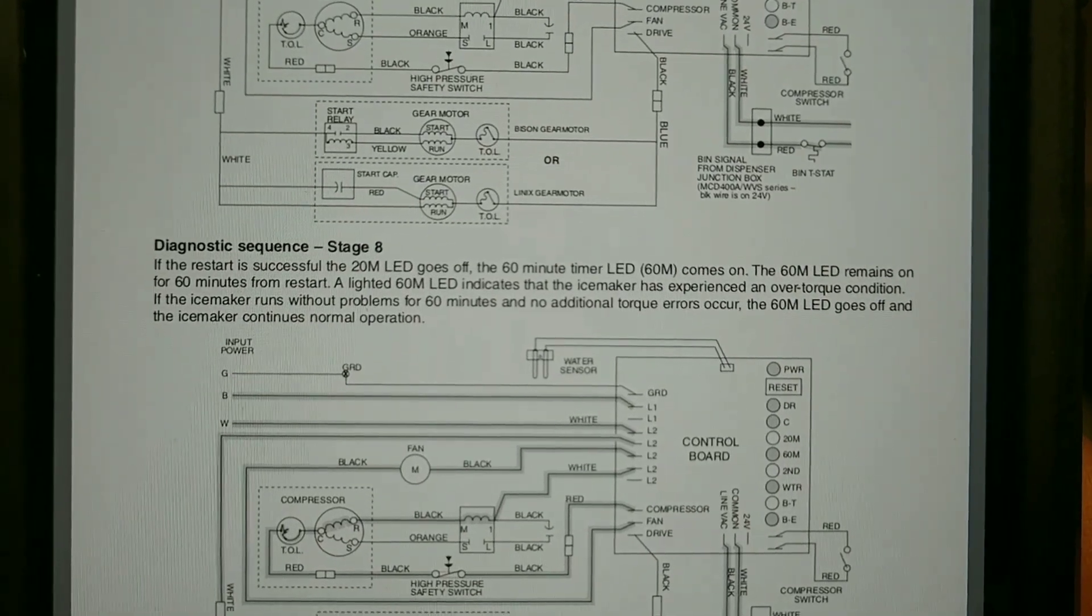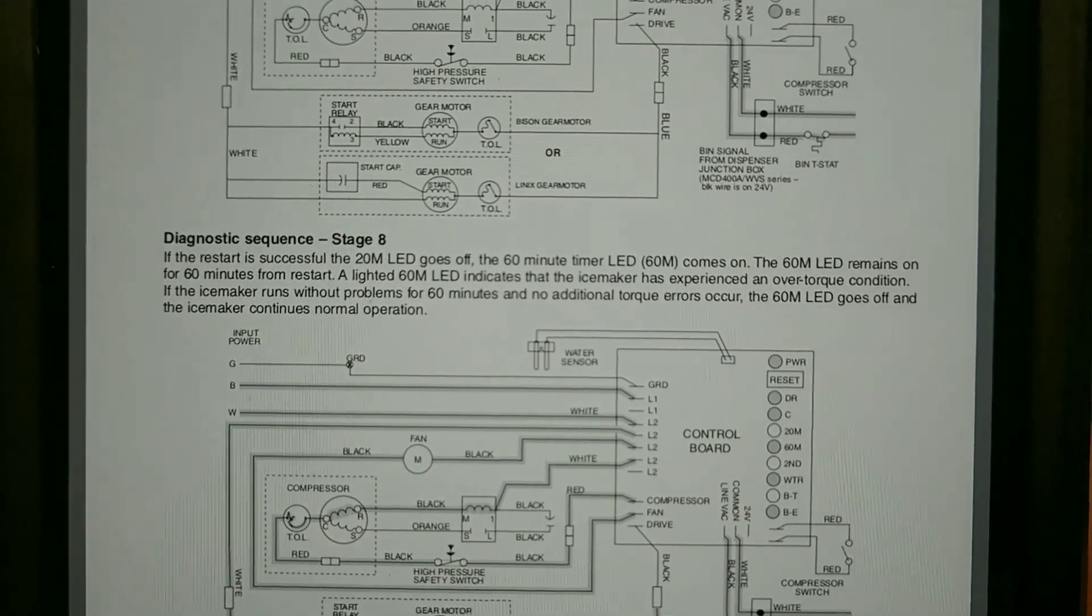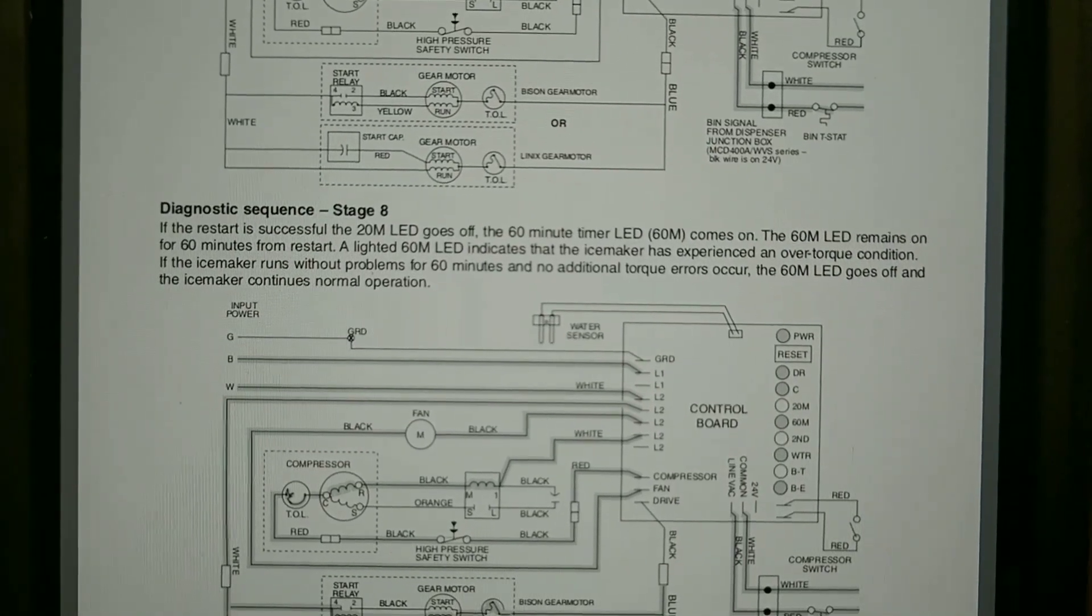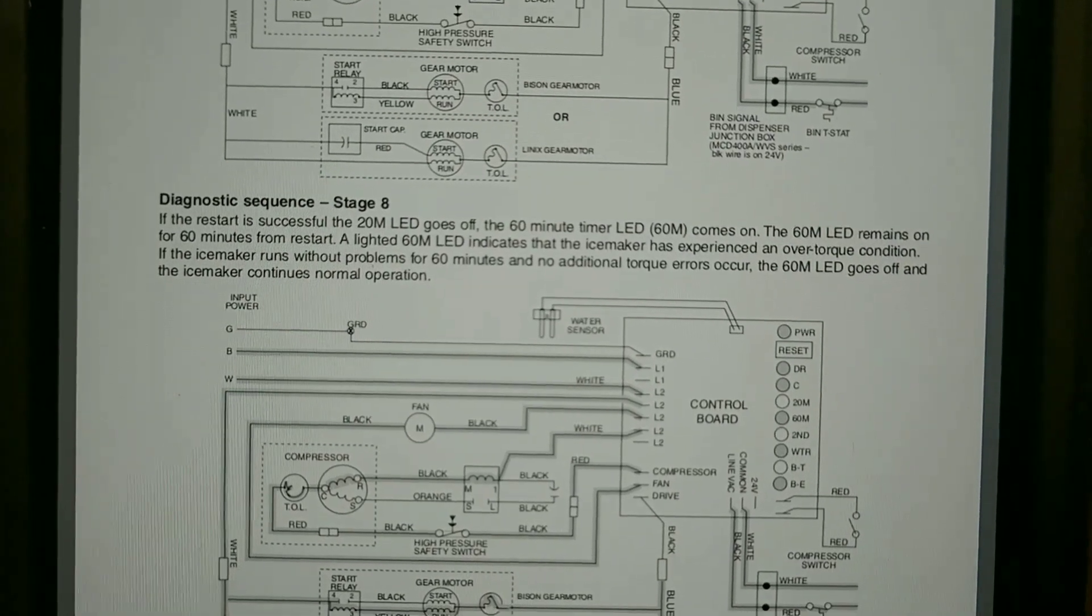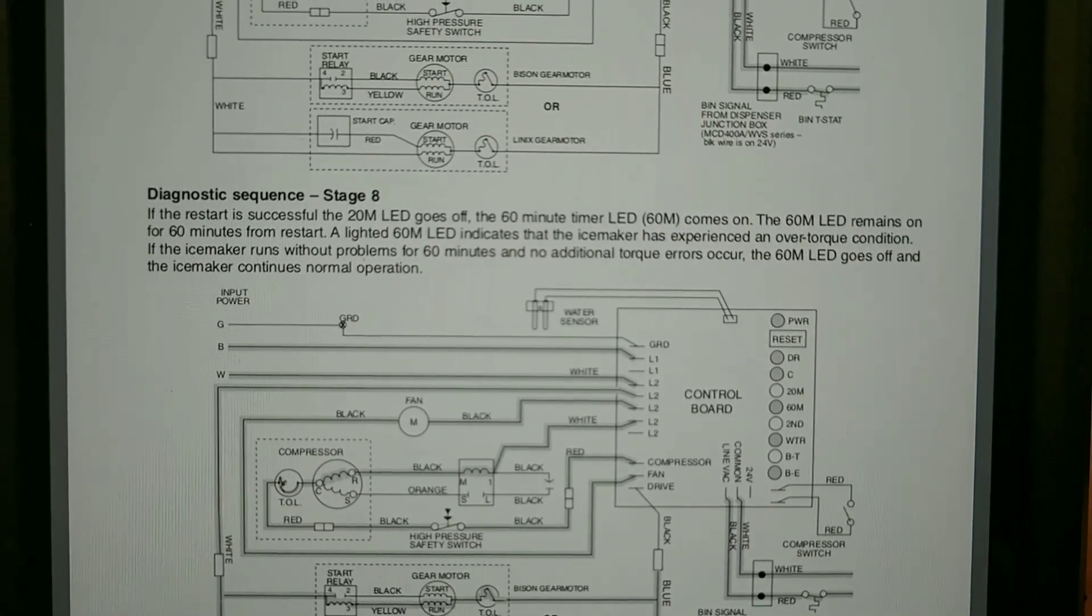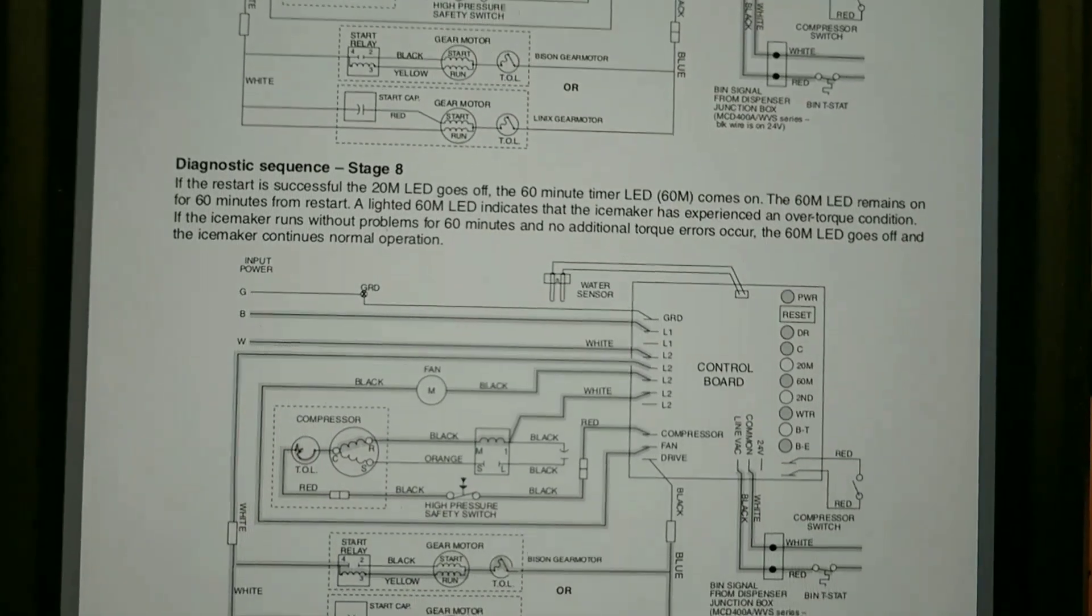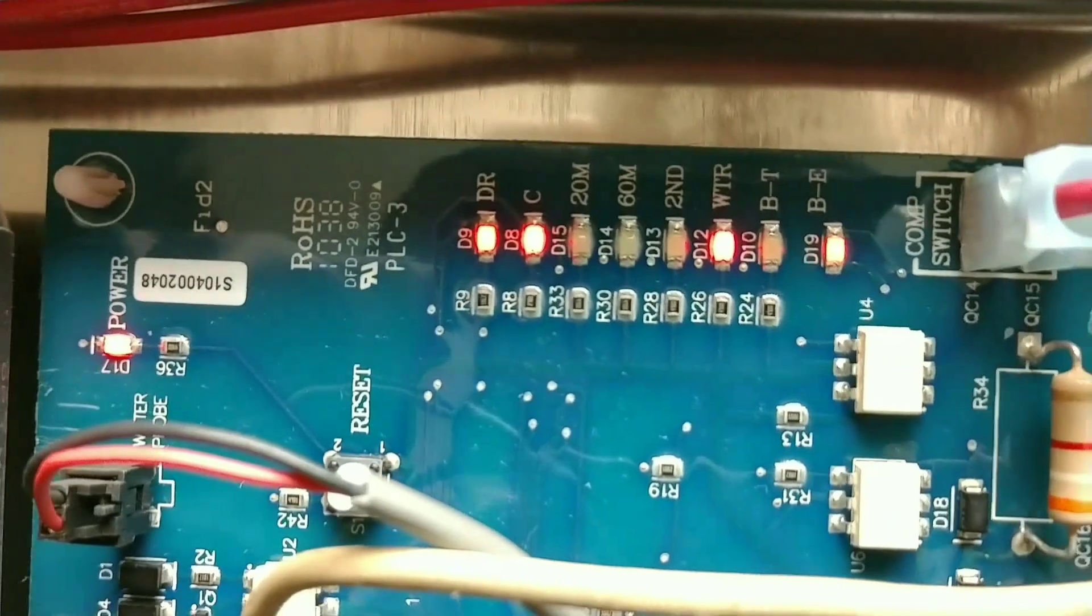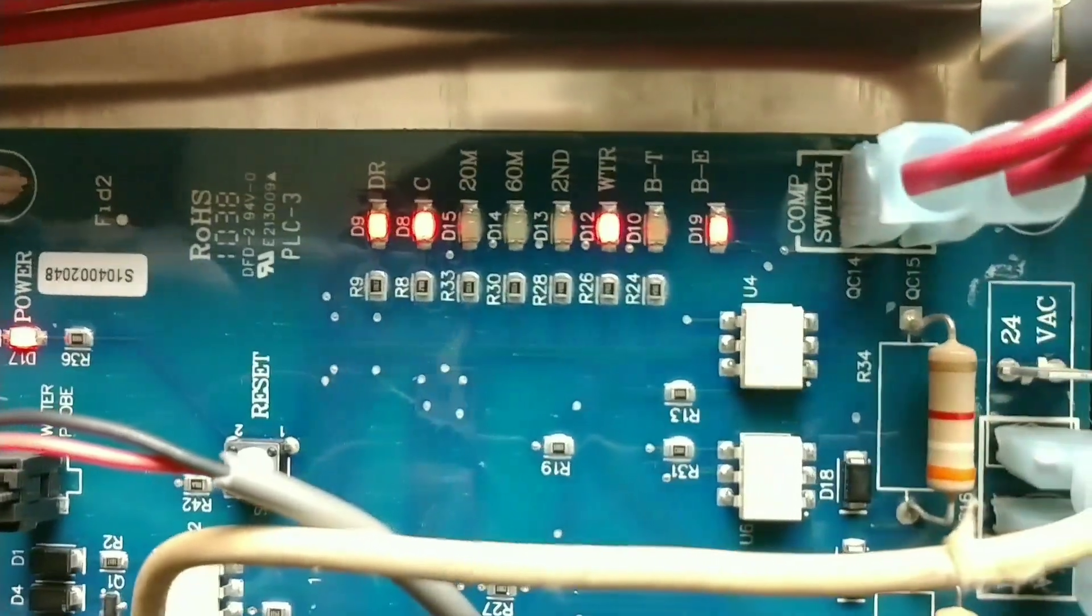The 60m LED remains on for 60 minutes from restart. A lighted 60m LED indicates that the ice maker has experienced an over torque condition. If the ice maker runs without problems for 60 minutes and no additional torque error occurs, the 60m LED goes off and the ice maker continues normal operation.